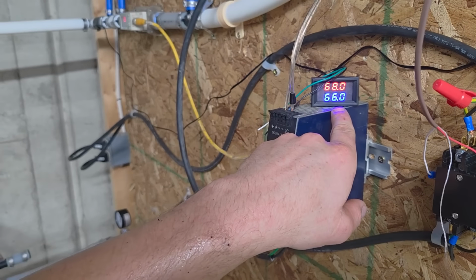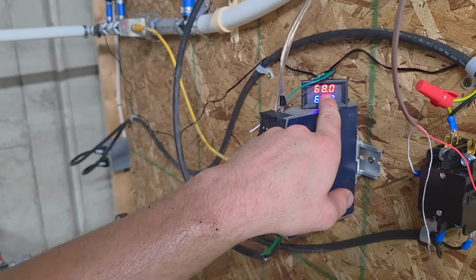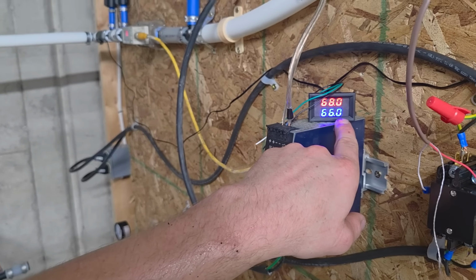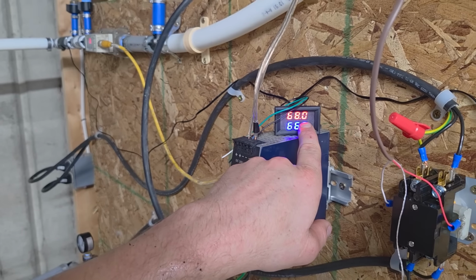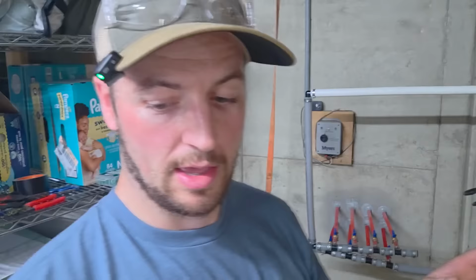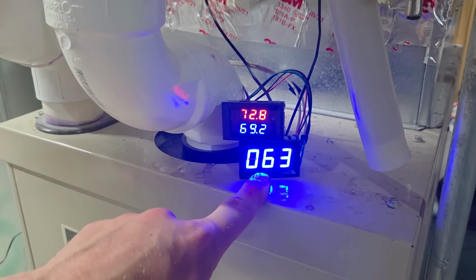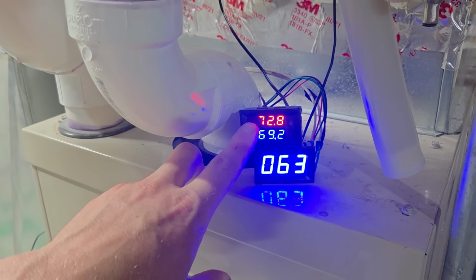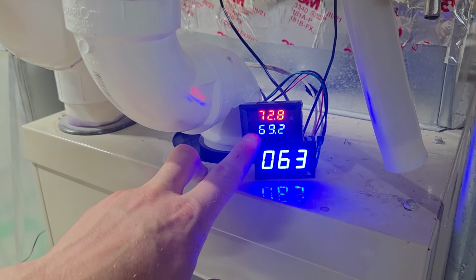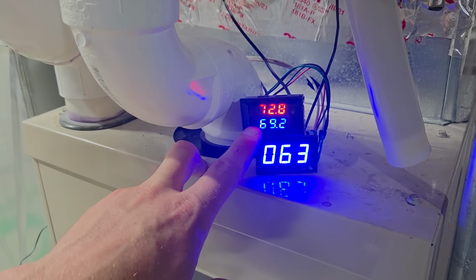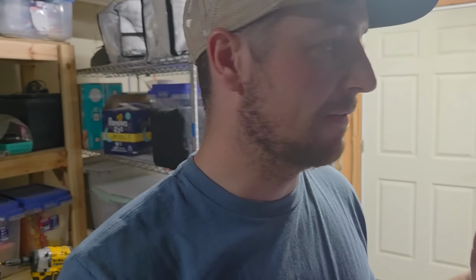20 minutes in, I apologize for being all sweaty and gross. It's hot outside and I'm working. This would be the water going into the loops, and this is the water coming back out. So what this number is showing me is that the water is increasing 2 degrees going through the ground loops. I don't know why it's so warm down there. That's a story for another time, but over here, our heat exchanger is reading 63 degrees. Our incoming air is 72.8 and our outgoing air is 69.2. Almost 4 degrees of temperature change. It's only been about 15 minutes.